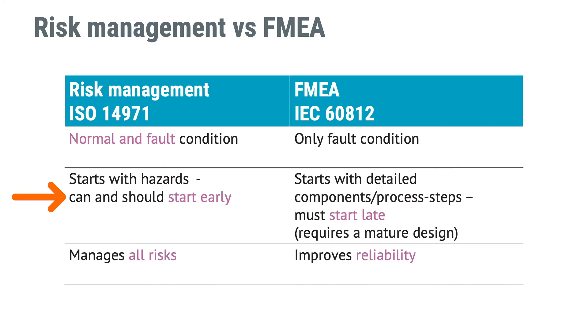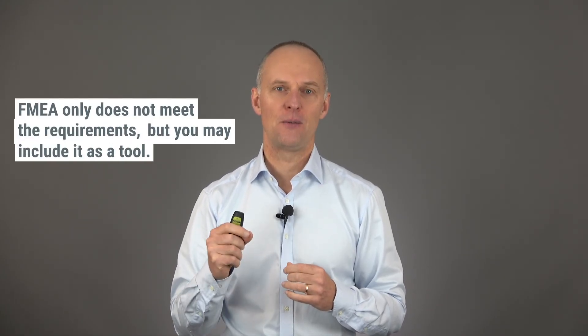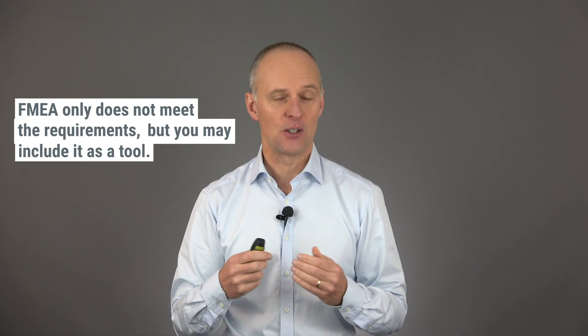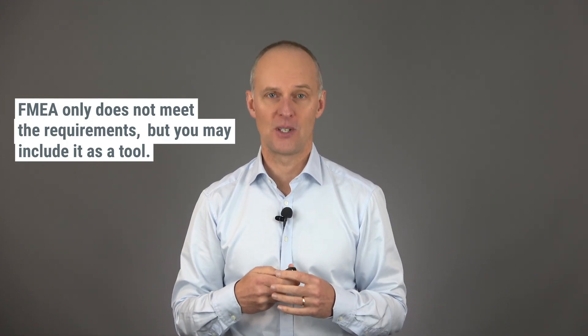ISO 14971 risk management, on the other hand, starts with hazards that can be identified at really early stages in the design life cycle. ISO 14971 will manage all risks from all life cycle phases — both normal use, reasonably foreseeable misuse, and in some cases even abnormal use — whereas FMEA only aims to improve reliability of the design or process. So if you only use FMEA, you do not meet the requirements of the ISO 14971 standard, which in turn usually means you do not meet the requirements of the medical device regulation, nor are you likely to meet the FDA's expectations on risk management in the US.